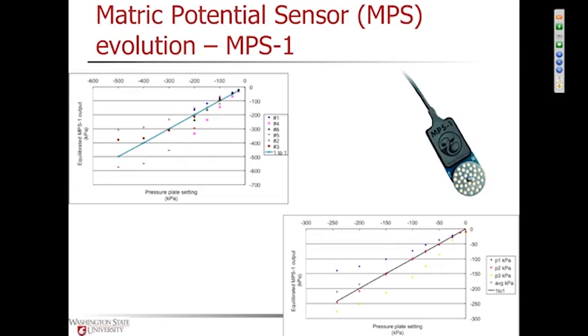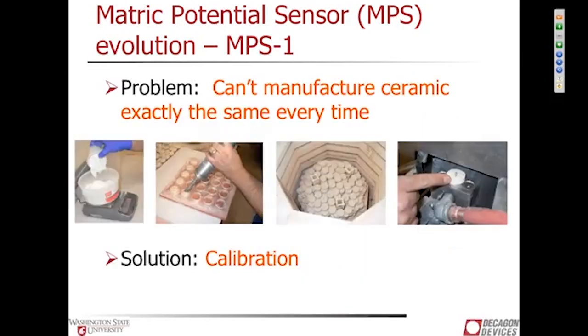And so we started looking at this quite a bit more and trying to figure out where this loss of accuracy was coming from. And it turns out that it is extremely difficult to make a ceramic material where each ceramic disc has the same moisture characteristic curve as all the other ceramic discs. So what we'd like is to have a universal calibration, where each sensor shares the same calibration. But to do that, each disc has to be exactly the same. And I'm sure that most of you have never tried to manufacture a ceramic with a wide and controlled pore size distribution before.